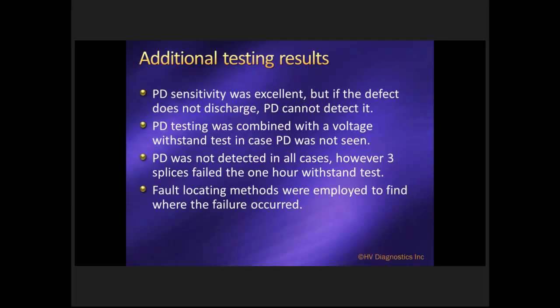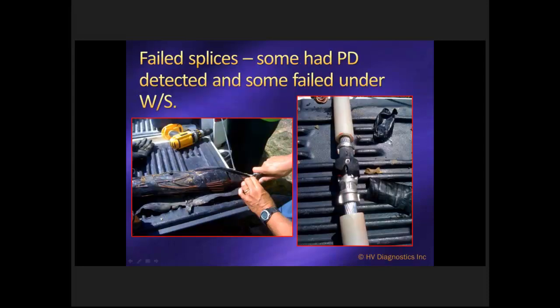Fault locating methods were used, and these failures were found. As you can see in the picture over here, the sharp edges of the barrel connector connecting the splice had completely cut through the strip material that they put around there, and it actually penetrated the splice volume. That's where it failed. What's interesting about this particular one is that some failed on the PD and some, as I mentioned, failed on the withstand test.